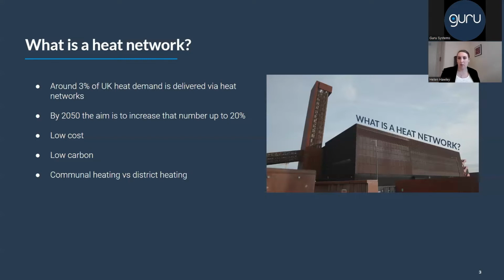The most important thing, however, is the way the system is designed. So with a single boiler, typically the system runs on an 80-70 degree output for heating and delivers domestic hot water at 60 degrees. So these are quite high thermal outputs. With district heating or heat networks, typically you will be looking to reduce those temperatures. So you don't tend to store domestic hot water in a cylinder, you tend to supply direct to the tap. And this means that you can lower that temperature to 50 degrees.